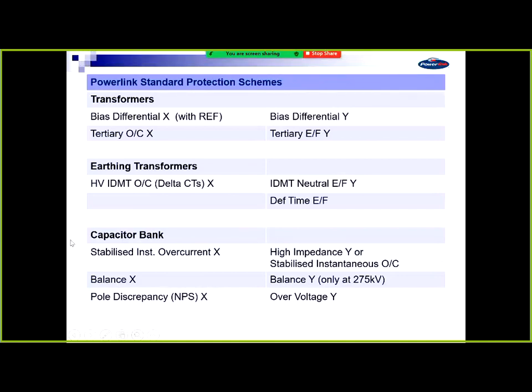So these are the typical types of protection that we have in PowerLink. For transformers, under the National Electricity Rules, there are 2 systems you must have, schemes for protection, both running high speed, both in competition with one another. So it's not a main and backup, which happens in the distribution network. We call it X and Y in PowerLink and across a lot of Australia. Some places around the world call it A and B, some call it main 1, main 2. It's all the same. Here the terminology is X and Y.